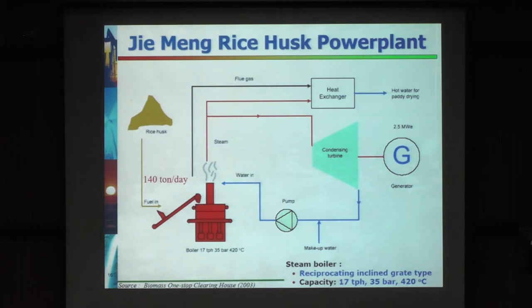These are some examples of a demonstration plant. This plant can produce power of up to 2.5 megawatts of electrical power. So we need to feed rice husk at about 100 tons per day to produce 2.5 megawatts of electrical power, and burn it in the boiler and then drive the steam turbine. For this plant, they use a combustor of the reciprocating incline grate type. And this plant needs to produce steam at about 17 tons per hour, with a pressure of about 35 bar and a temperature of 420 Celsius.